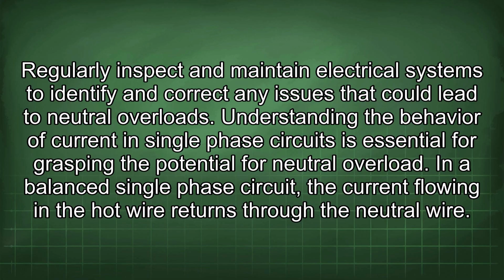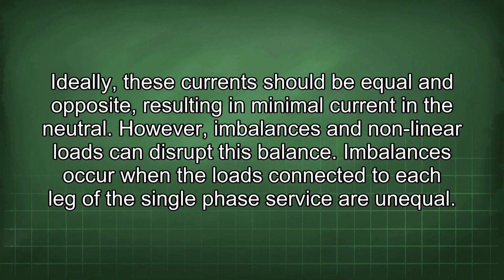Understanding the behavior of current in single-phase circuits is essential for grasping the potential for neutral overload. In a balanced single-phase circuit, the current flowing in the hot wire returns through the neutral wire. Ideally, these currents should be equal and opposite, resulting in minimal current in the neutral. However, imbalances and nonlinear loads can disrupt this balance.